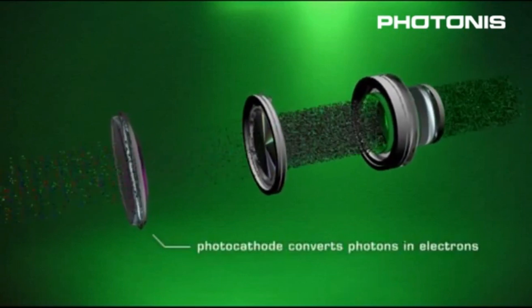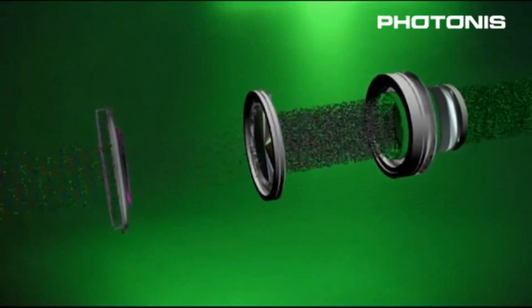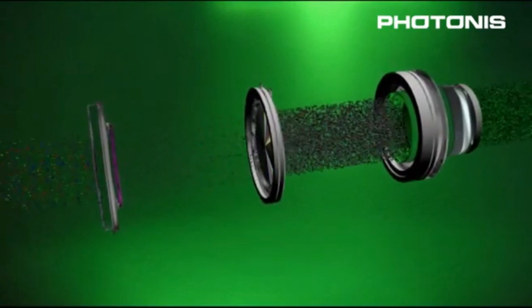Image intensifiers convert low levels of light photons into electrons, amplify those electrons, and then convert the electrons back into photons of light.